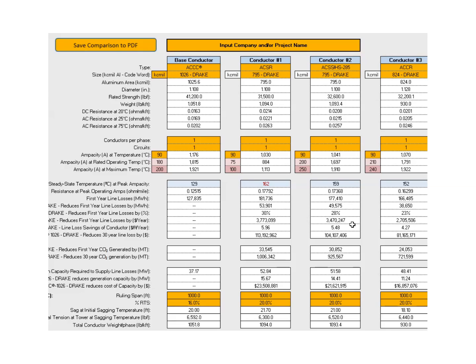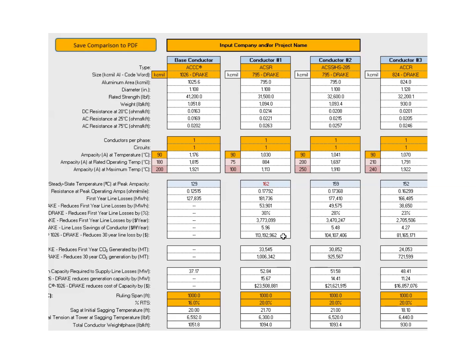Now, you can also translate these savings into what does that equate to per conductor foot. So in this case, over ACSR, we're saving about $5.96 per year over ACSR of the same size, which is about 130%, 140% of the actual cost of ACCC conductor. So this would basically indicate that if you replace ACSR with ACCC, the line loss reductions alone would pay for itself in less than a year, maybe six or seven months. Over a 30-year period, we're looking at about $113 million savings in line loss reductions compared to ACSR using ACCC. $104 million improvement over ACSS, HS285 or ACSS period. About $81 million savings in line loss reductions compared to 3M's product.